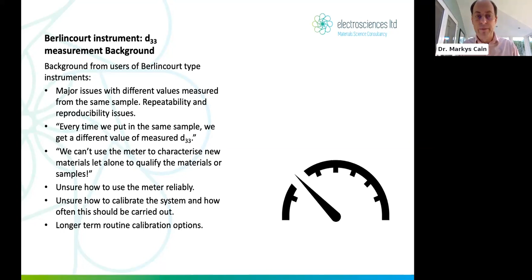This is the piezo test d33 meter. This is how it works. Hopefully you can see my mouse. This purple thing here is the piezoelectric specimen, and we have loading contacts, top and bottom. Now a piezo material, when we stress it, it generates an electrical charge, okay? And we measure that electrical charge using some electrometer or some charge meter, or maybe we measure a current, and integrate that to get charge.